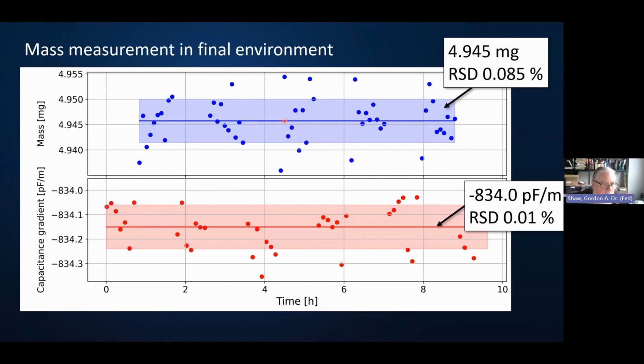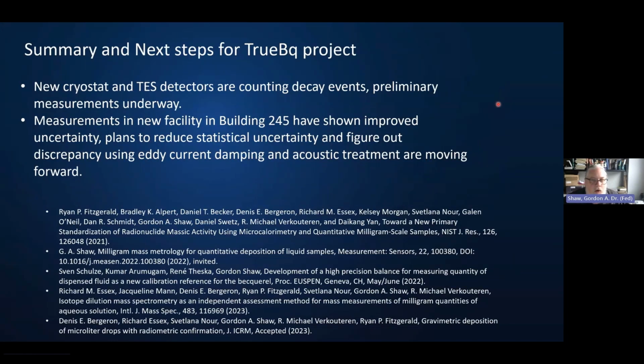Preliminary measurements have been done using a wire mass that we calibrated here at NIST. We see that in this case, we're able to measure the mass of the wire with less than 0.1% relative standard deviation. The accuracy is also less than about 0.1%. And so this work is in progress. We've demonstrated that we can do this for a wire mass. Now we are working on demonstrating that we can do the same accuracy for a liquid sample. And we're working on various strategies, including eddy current damping and acoustic treatment, to reduce our noise and improve the uncertainty.